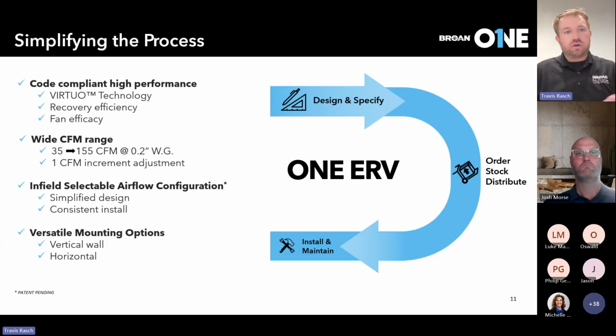It's going to move that heat from hot to cold and that moisture from wet to dry, depending on which side of the recovery core those two conditions are held. We'll tease this a little bit. We do have a performance calculator tool launching shortly, where you can refine those inputs and see exact results for your project location, with the product specified, the CFM, static pressure, etc. You'll get exact results for recovery efficiency, dry bulb, wet bulb, enthalpy recovery ratio, and so on. So I'll leave it as a bit of a teaser, and we'll cover that performance calculator at the end to help solidify the answer.